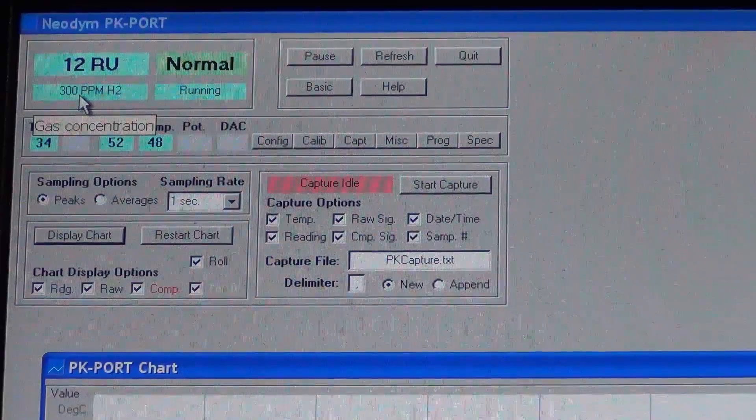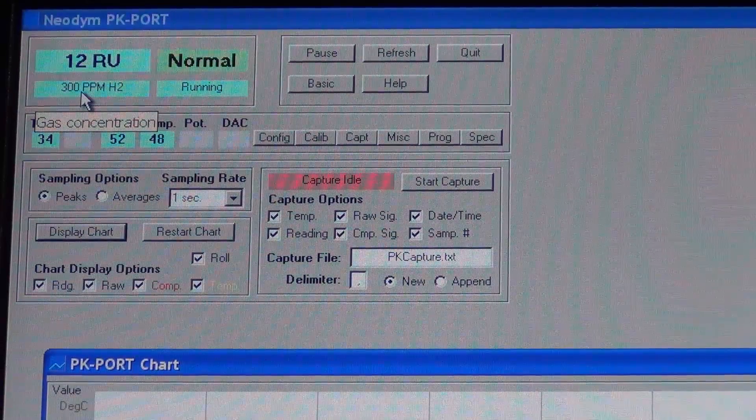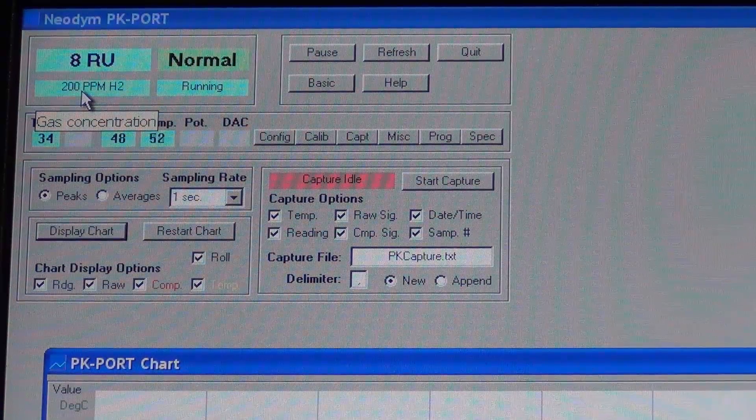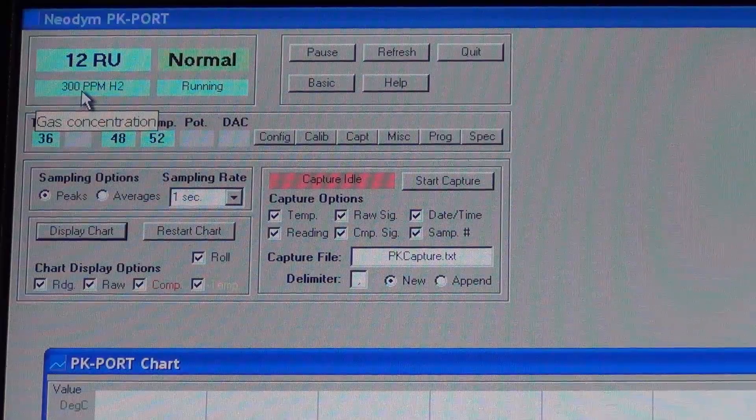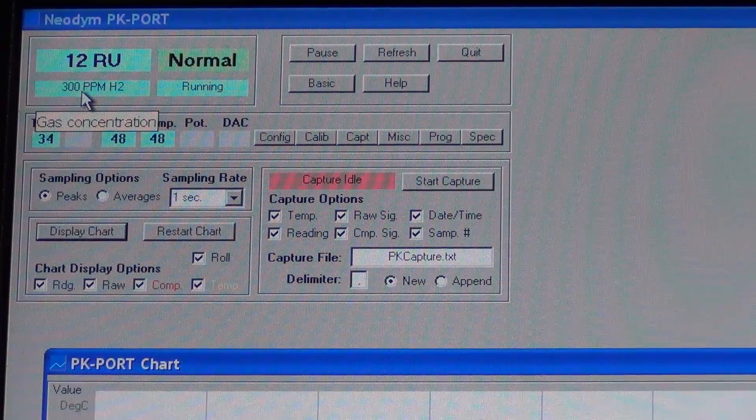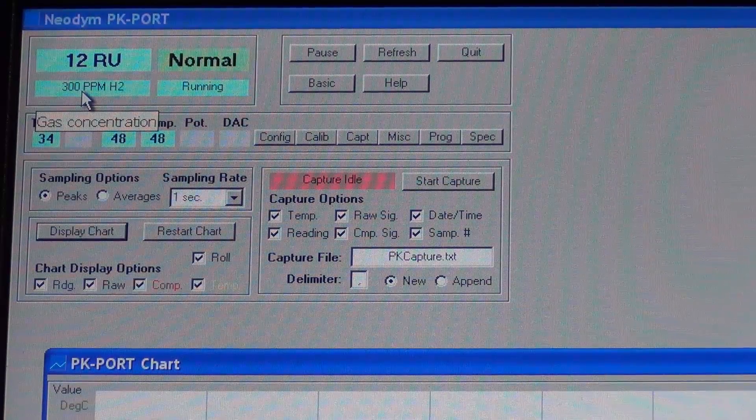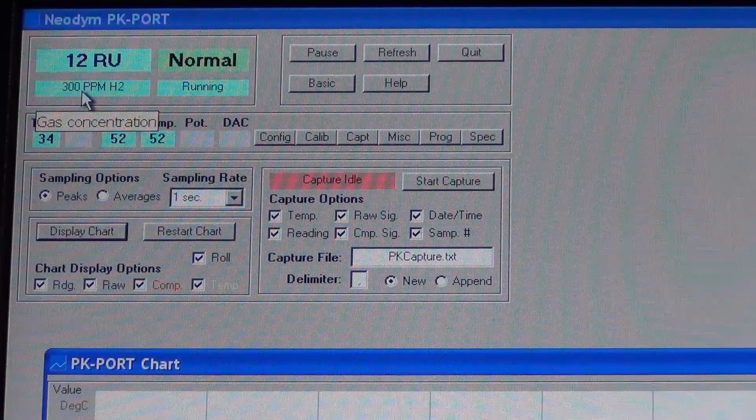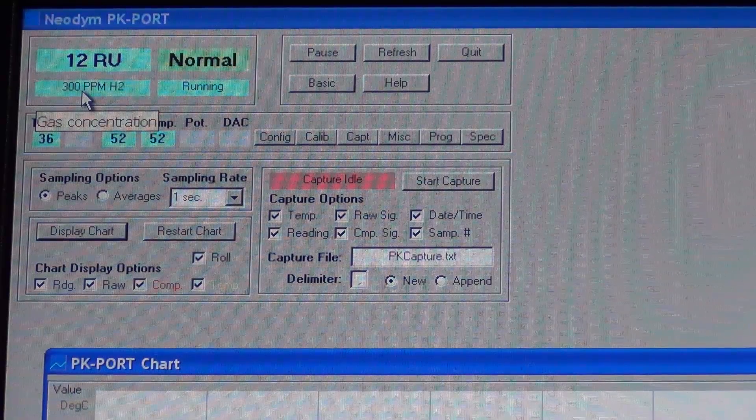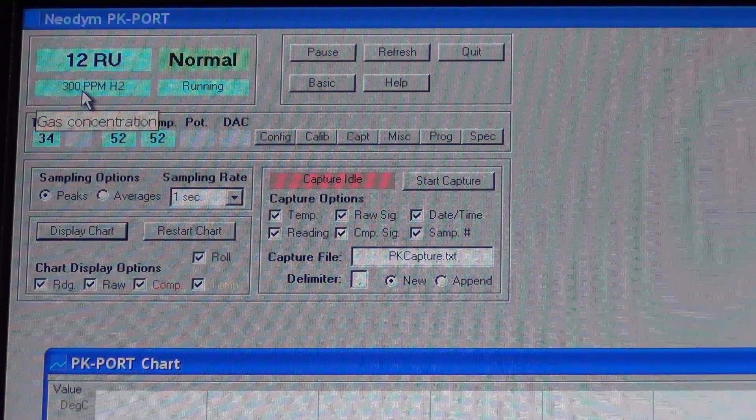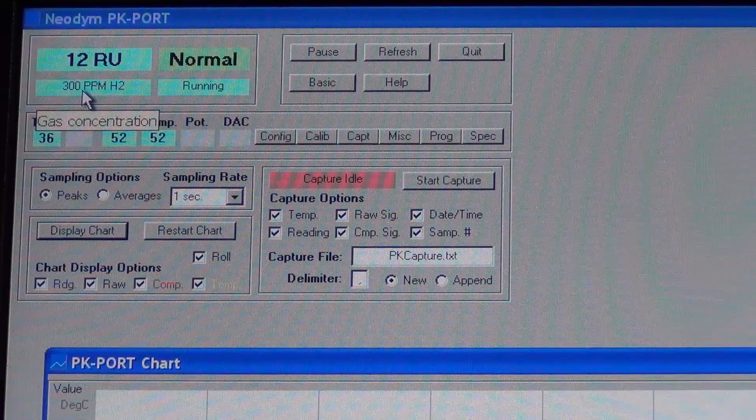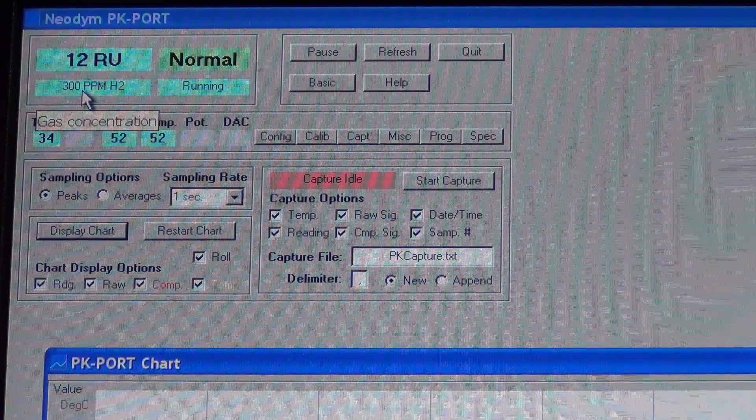And what we're going to do is we're going to start charging this basically through a bulk and absorption. And during that time, we're going to watch to see how this number climbs. Now, 40,000 ppm would be 4%, which is the trigger point, which you want to definitely stay below because that's where hydrogen gas can actually ignite.